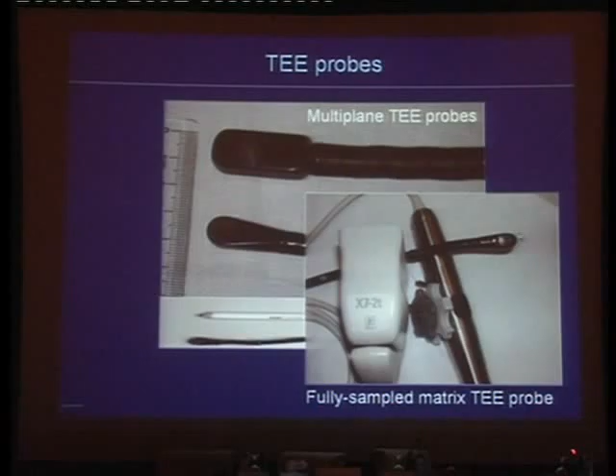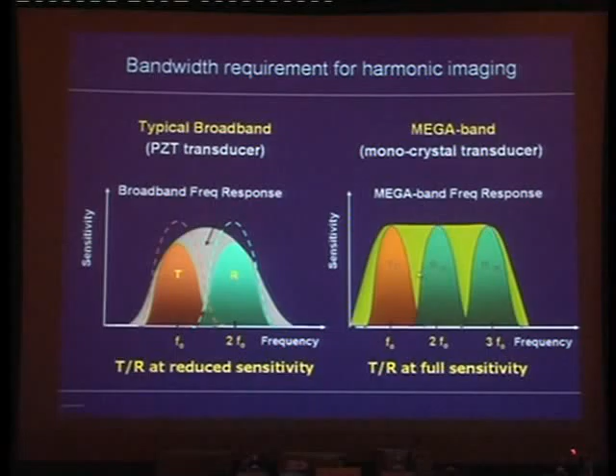So you can make them smaller to have the same performance, and of course you have much less interaction between crystals and much less noise. So these transducers can be made smaller, are more sensitive, and you avoid the noise in your image. Now the multiplane probe is the result of that. These are monocrystals, so they can be made very small for volumetric acquisition. The other advantage is that they are megaband transducers, so for many applications, harmonic imaging, superharmonic imaging, and in contrast studies, they also offer major advantages.